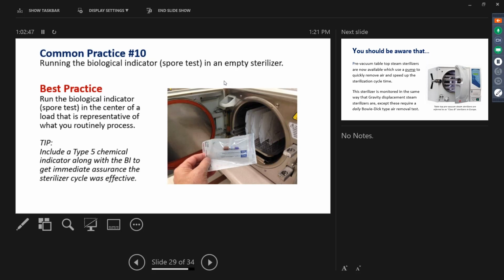Or what about all those other loads that you only test once a day or once a week? It would be best practice to use some type of indicator, not just your autoclave tape. They love the convenience and the cost of autoclave tape, but they're going to love a Type 5 indicator for a steam sterilizer based on science, regulatory, and legal standards.